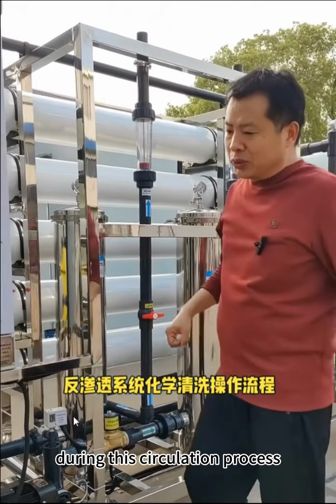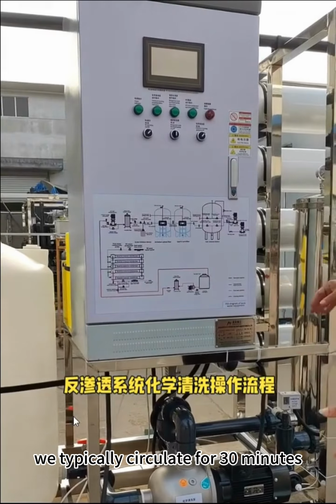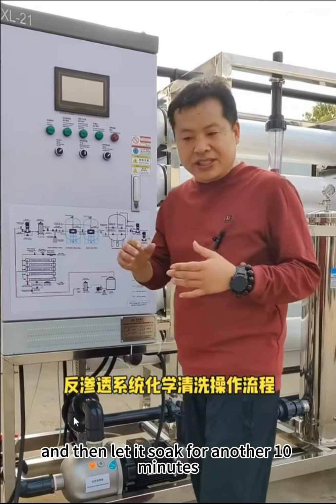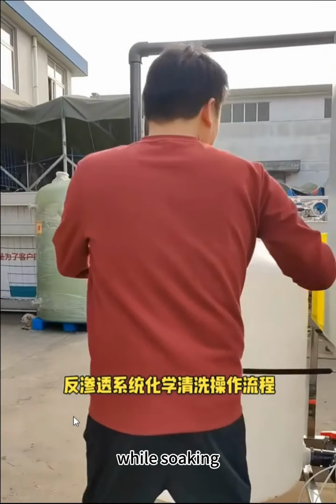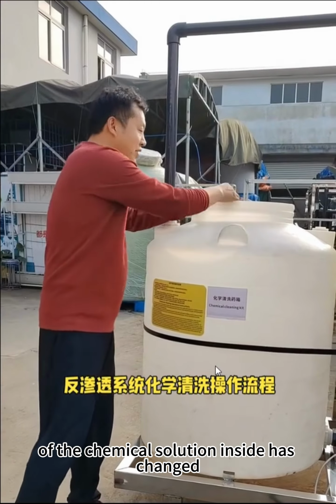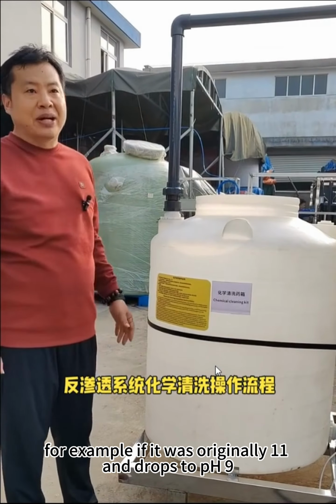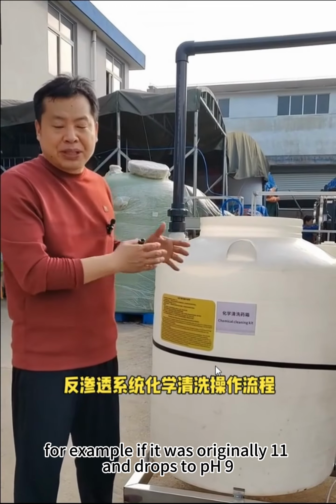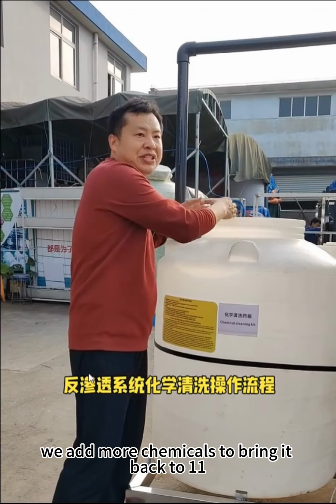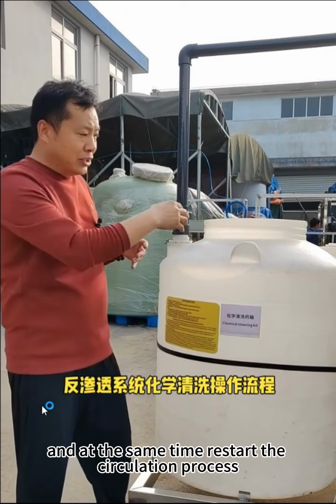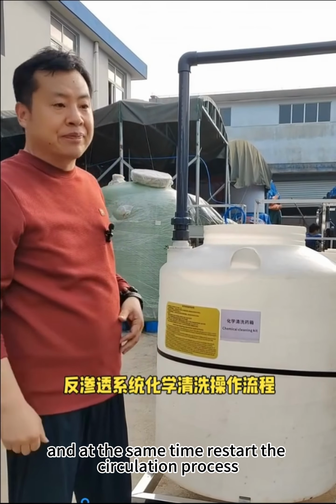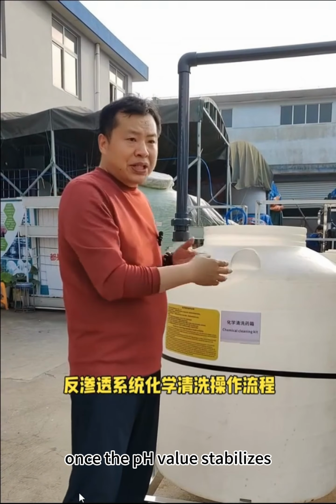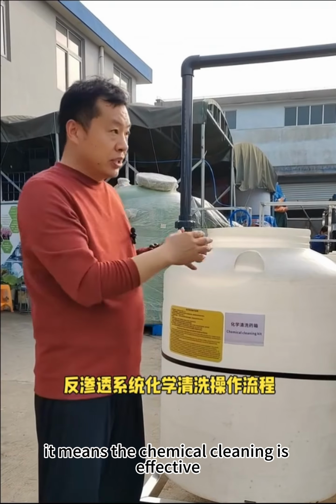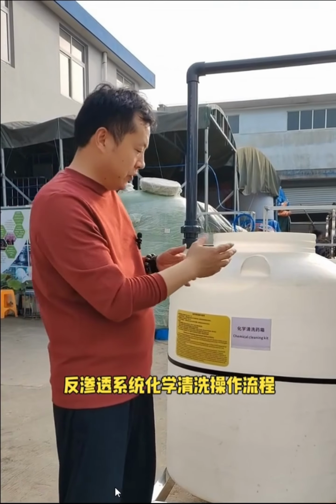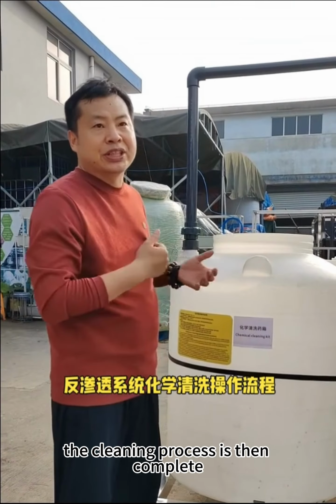During this circulation process, we typically circulate for 30 minutes and then let it soak for another 10 minutes. While soaking, we check whether the pH of the chemical solution inside has changed. For example, if it was originally 11 and drops to pH 9, we add more chemicals to bring it back to 11 and at the same time restart the circulation process. Once the pH value stabilizes, it means the chemical cleaning is effective. The cleaning process is then complete.